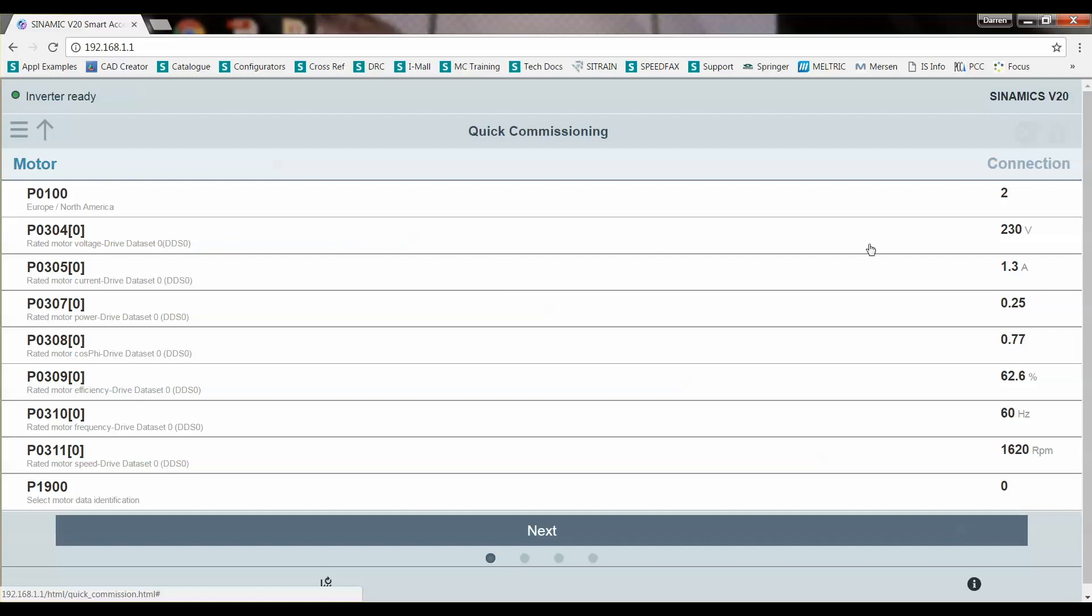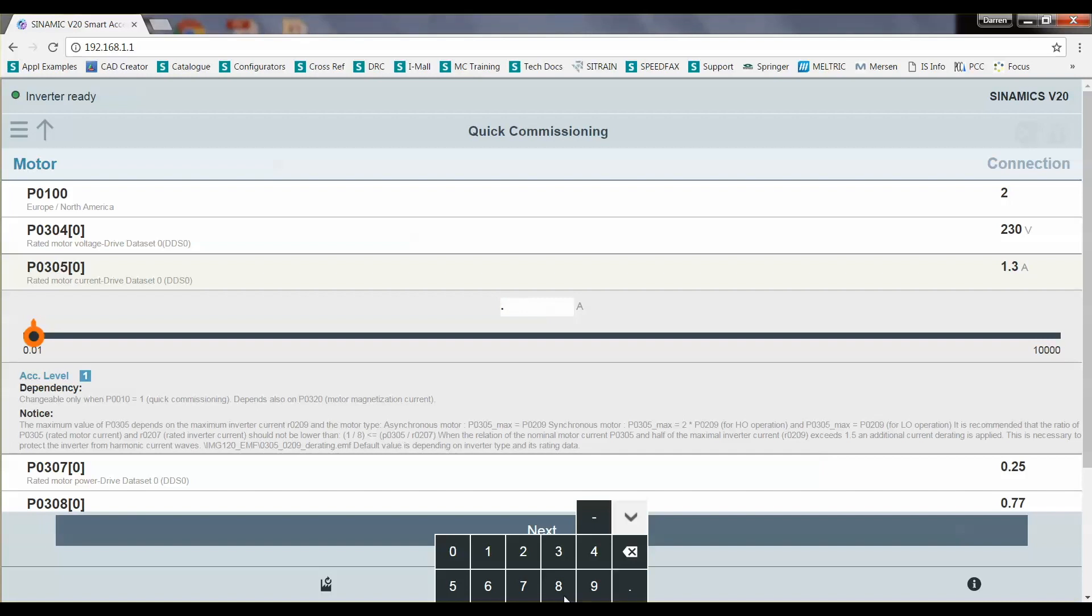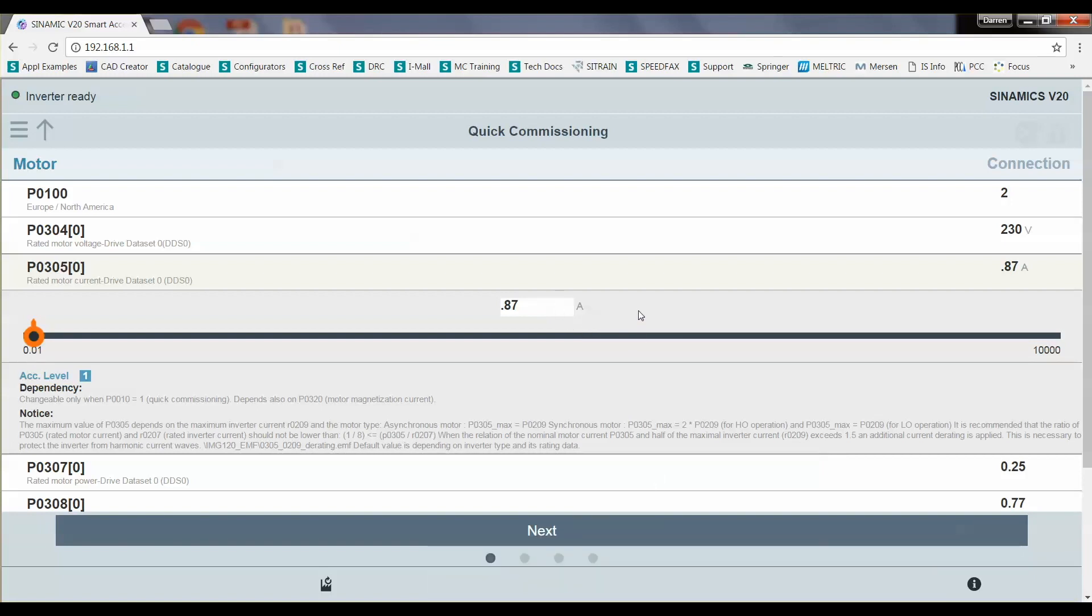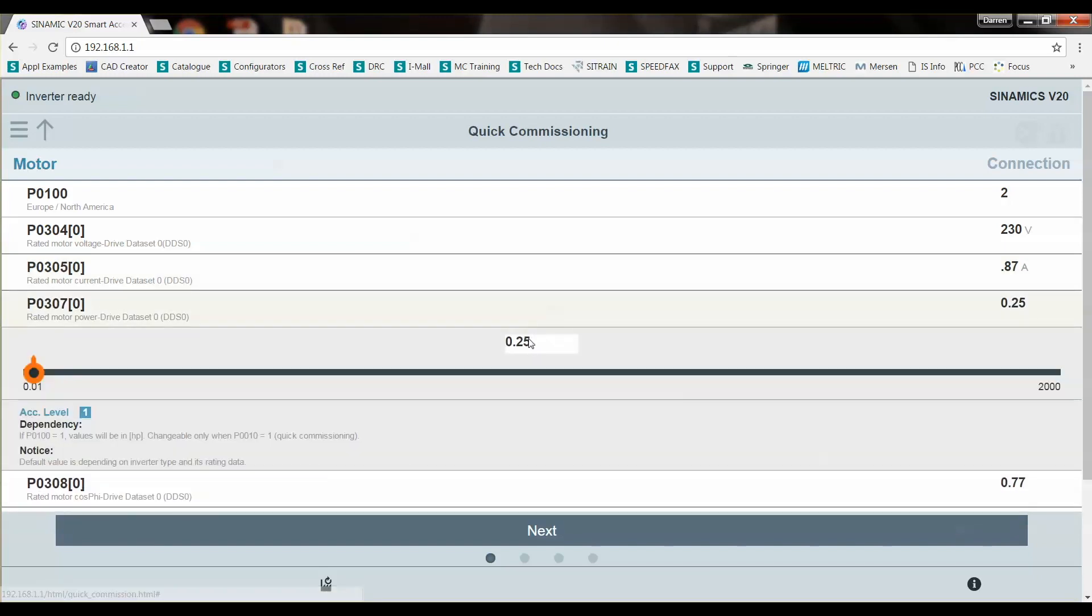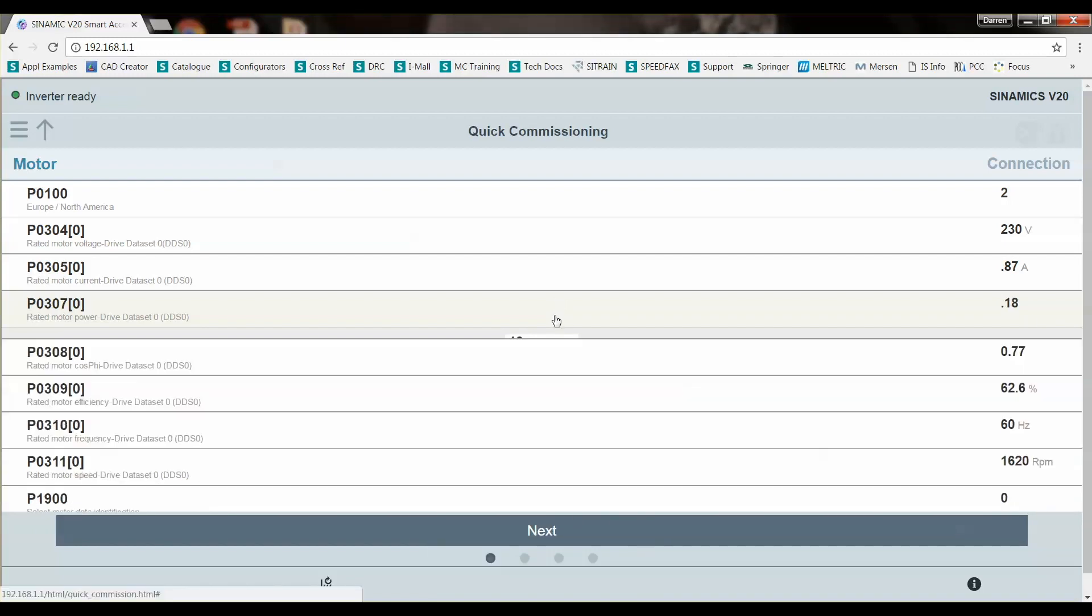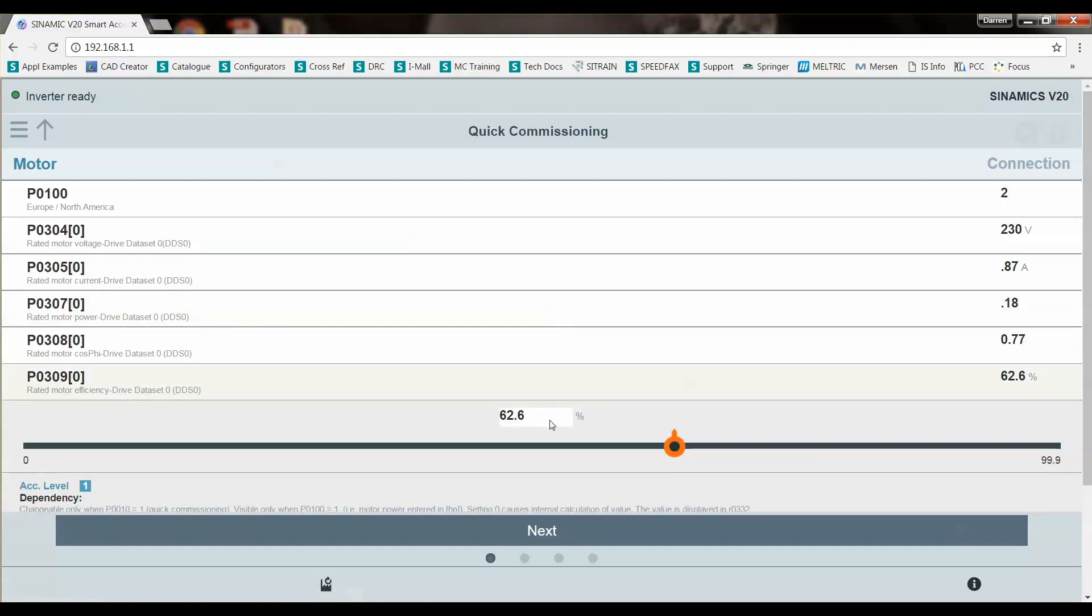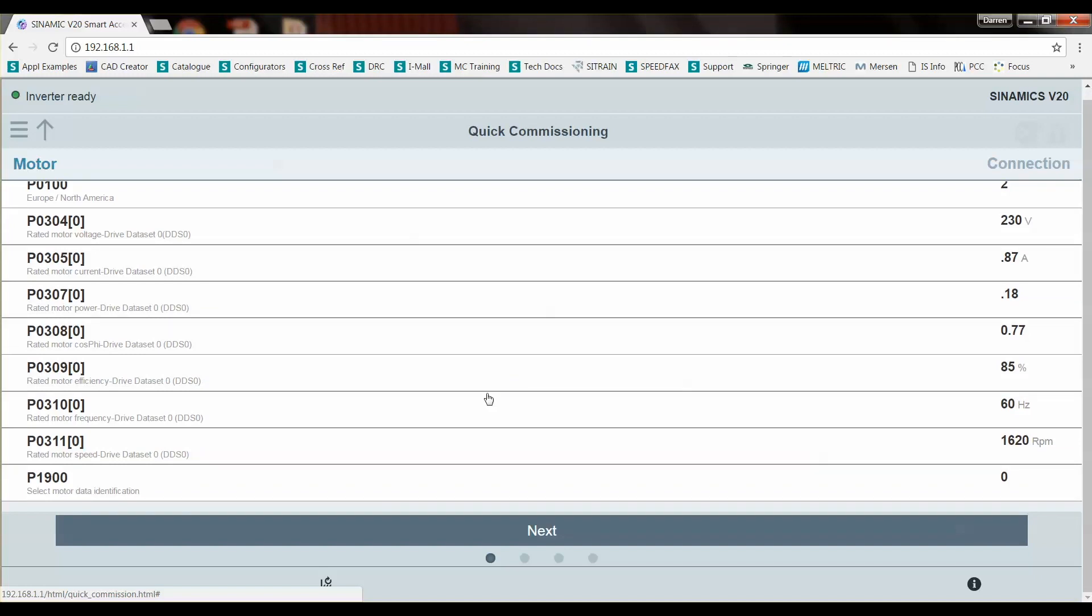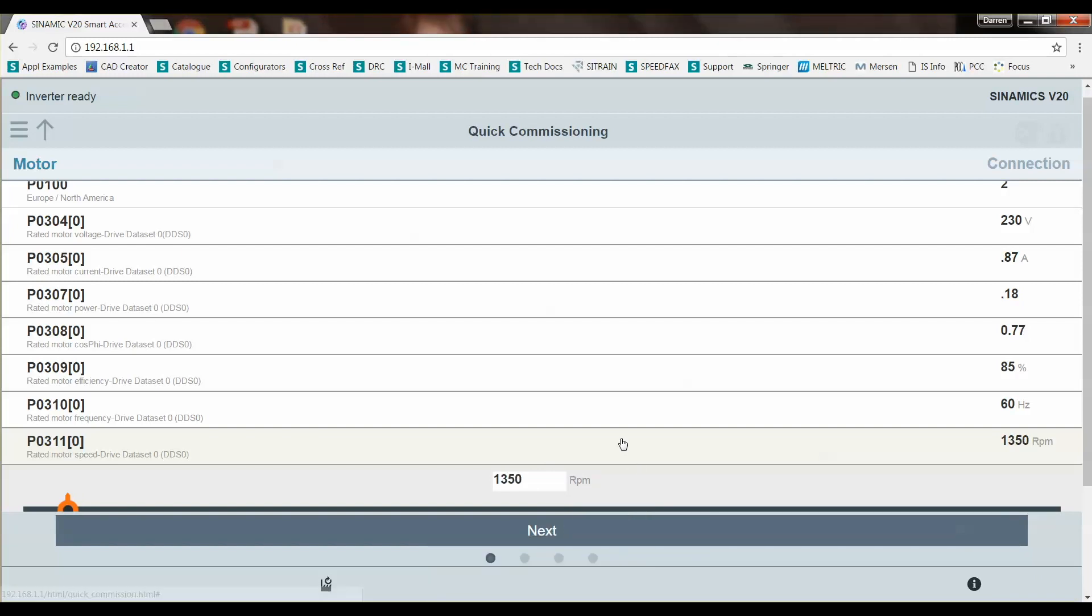That's good. Motor current is 0.87. Rated motor power is 0.18 kW. Cosine phi 0.77 is correct. Efficiency is 85 percent. Rated motor frequency is 60 hertz. Speed is 1350 rpm.